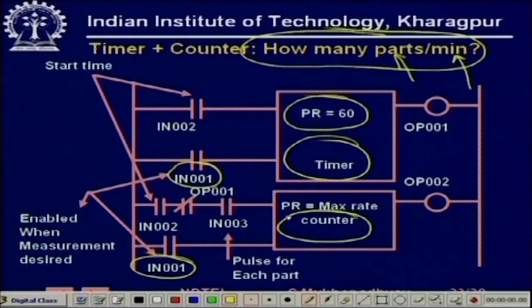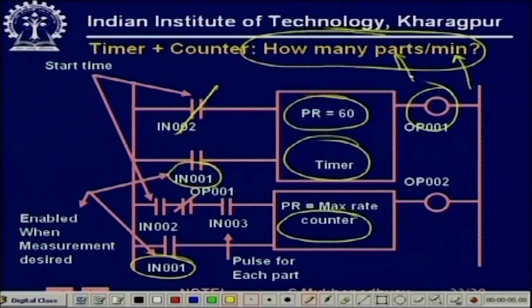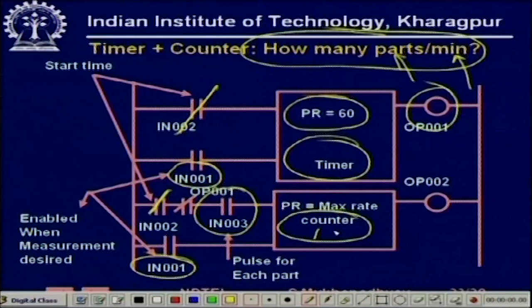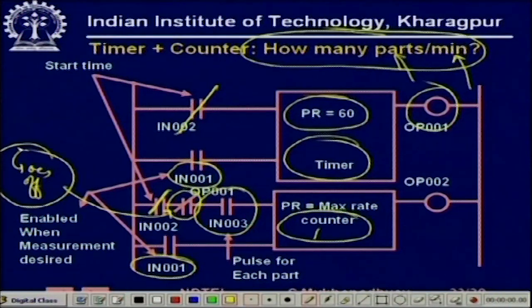When you say start — this is the master switch — and you want to know within this time how many parts have passed. You start the timer, this goes high, and every time a part arrives you get a pulse, so the counter goes up. In the meantime, after the time has expired, OP001 goes off, so this goes to 0 and further parts are not counted.